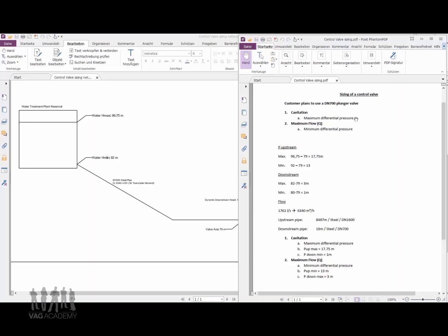The customer plans to use a DN700 plunger valve just before the reservoir. Our upstream pressure is the elevation — the maximum elevation of the tank minus the elevation of the valve — giving us the maximum upstream pressure of 17.75 meters. The minimum is the 92-meter minimum reservoir elevation minus the valve elevation, giving us a minimum upstream pressure of 13 meters. On the downstream side, the 82-meter elevation minus the valve elevation gives a maximum downstream pressure of 3 meters, and the minimum elevation gives a minimum downstream pressure of 1 meter.